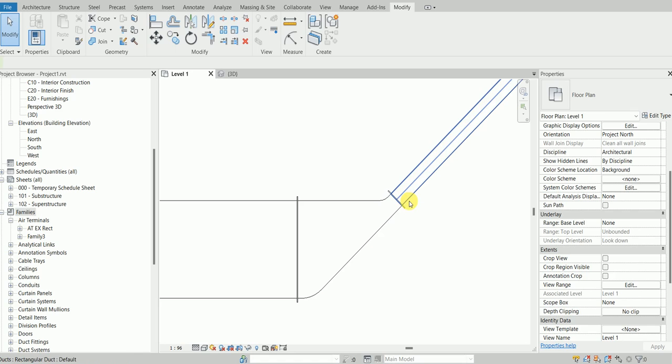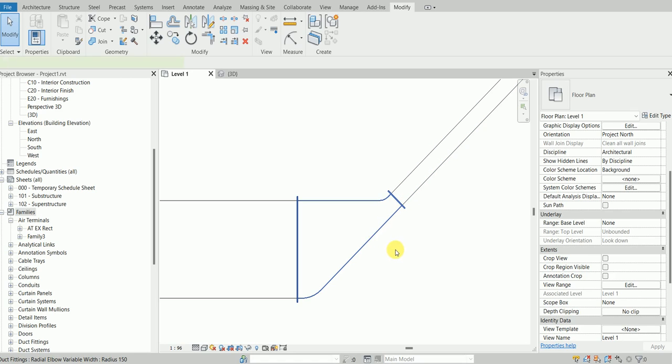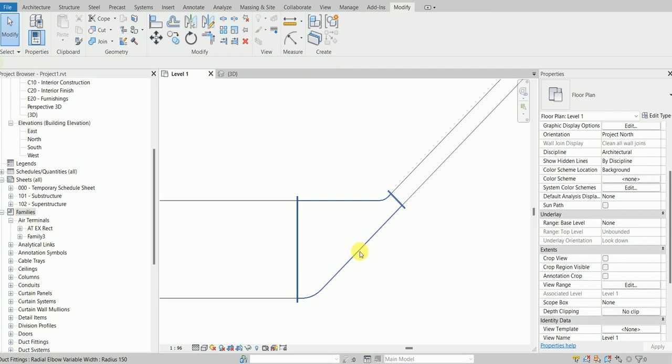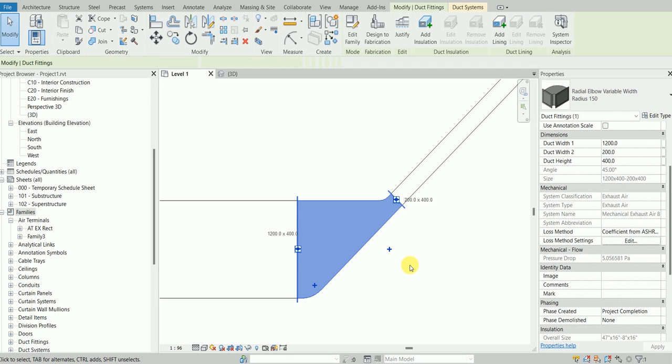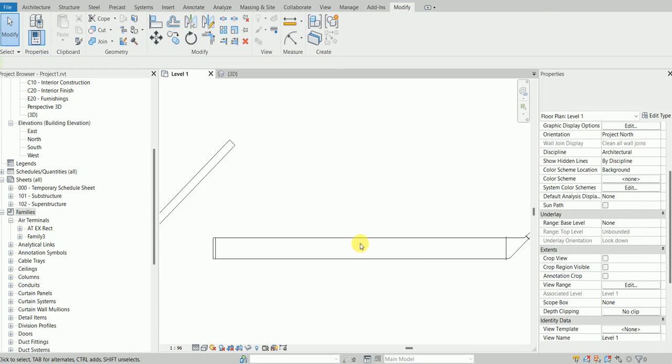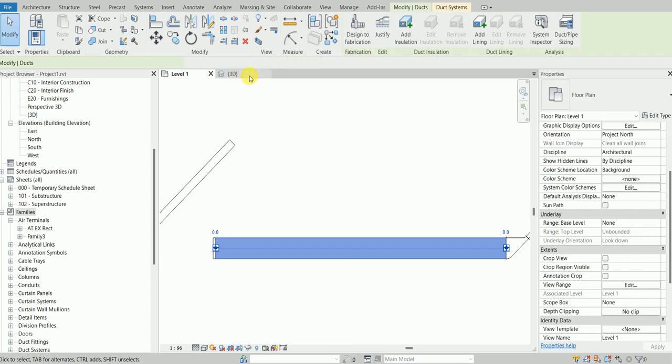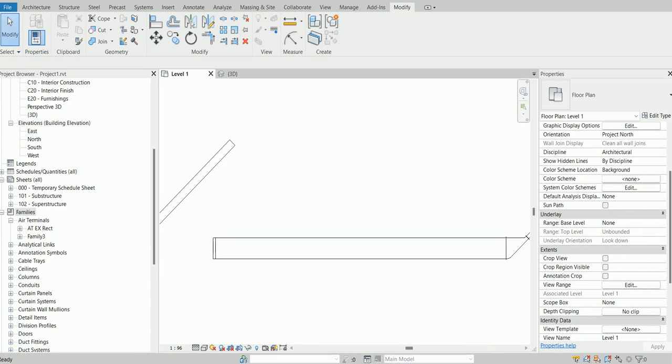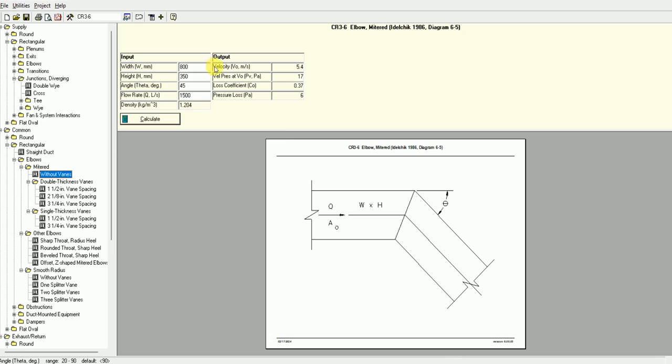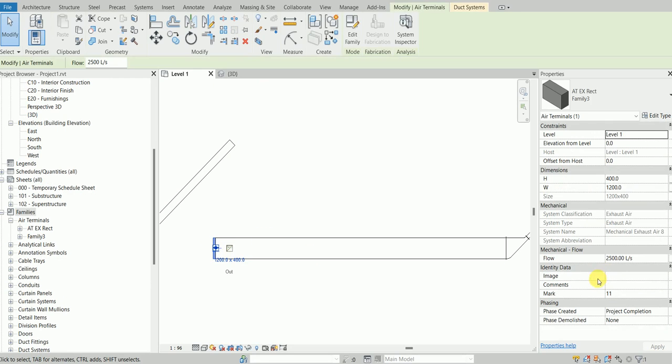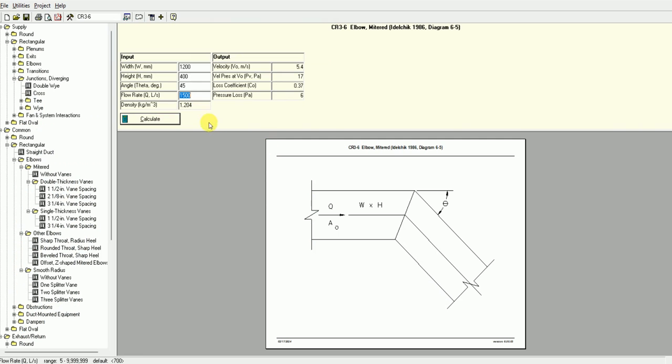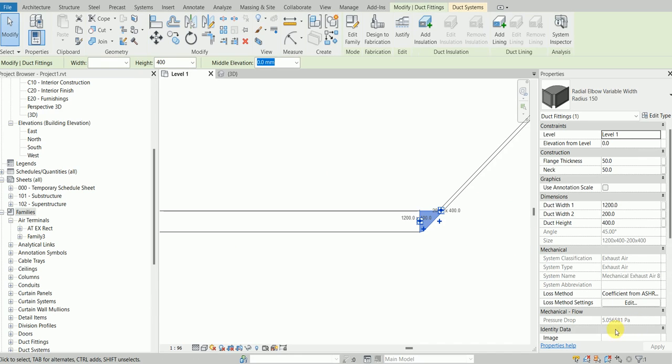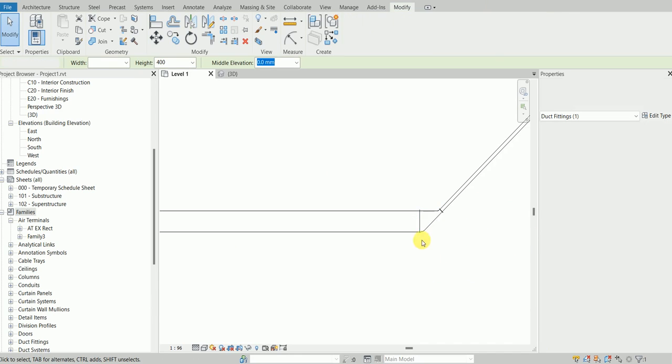It should have very huge pressure drop, but as no such shape exists in ASHRAE, we have to live with that. This is 1200 by 400, so let's go here: 1200 by 400. It was 1500, so the pressure drop is 6 pascals and yes, here it's like 5 pascals.